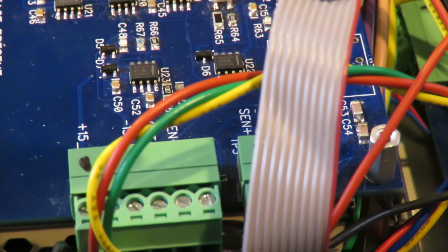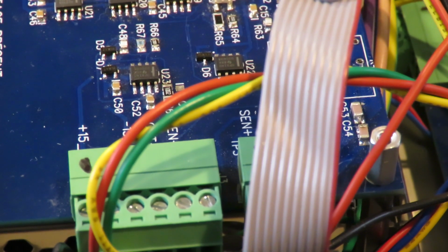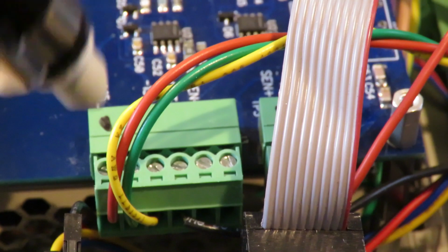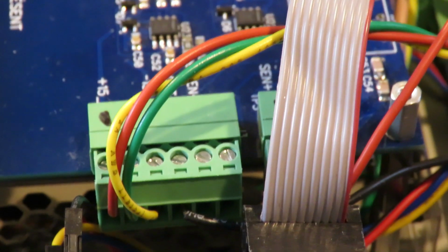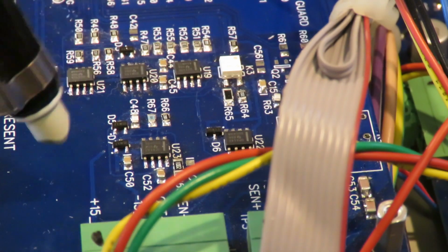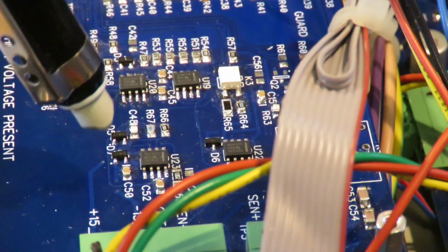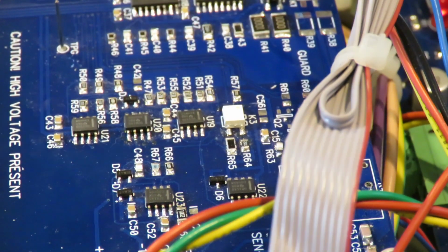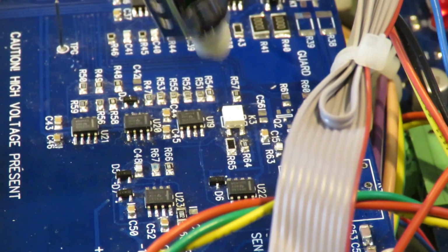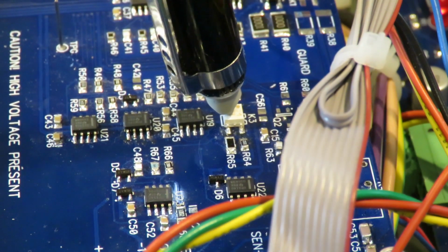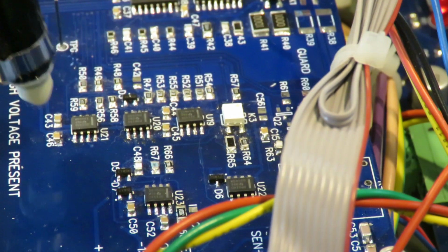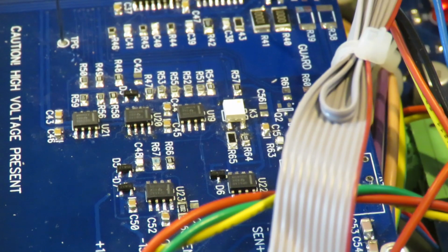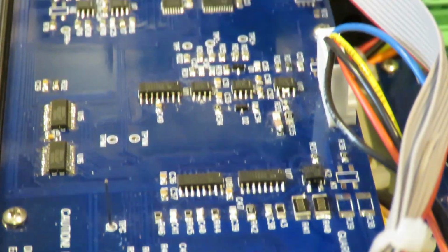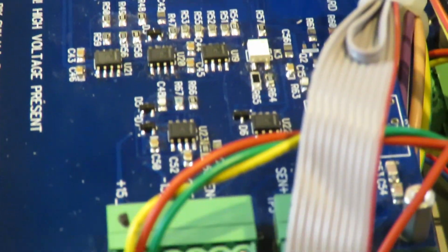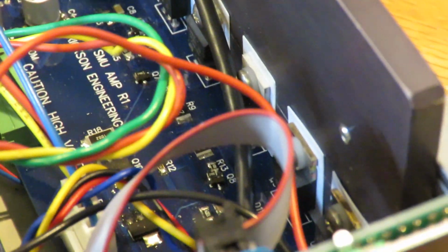These green connectors are for the output and remote sense connections. Also, these 3 wires interface to the amplifier board. These op amps here are the voltage sense, remote sense amplifiers. This solid state relay, the white guy, is for the voltage ranging. That switches to the 100 volt, 150 volt, or the 15 volt range, and down here are the difference amps for the current and voltage. So yeah, that's the main board.